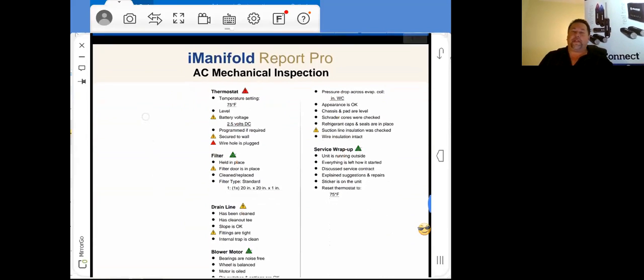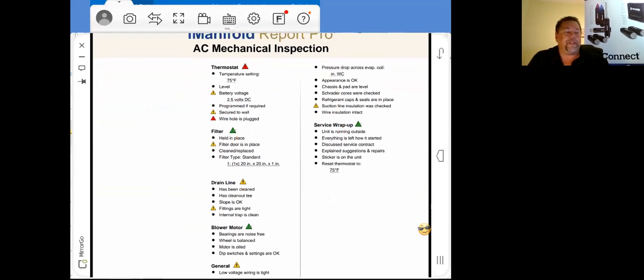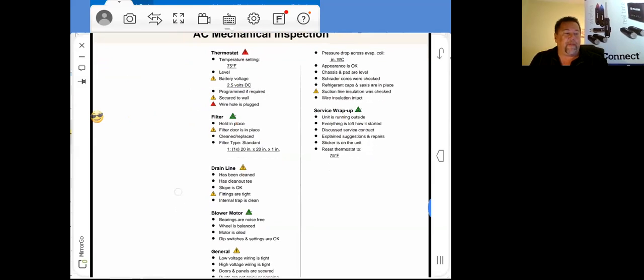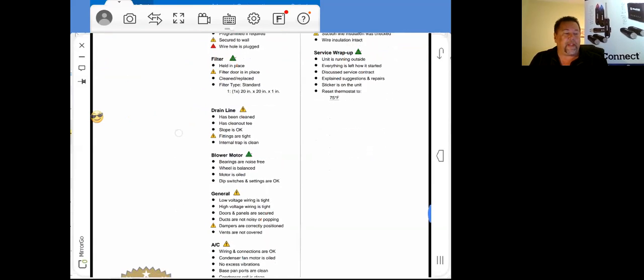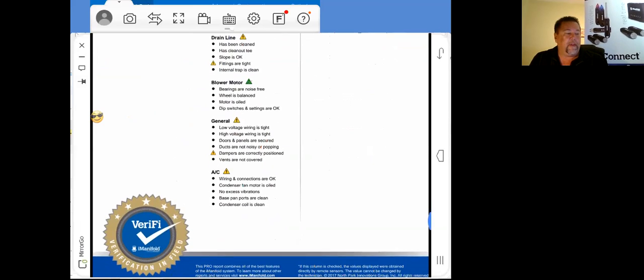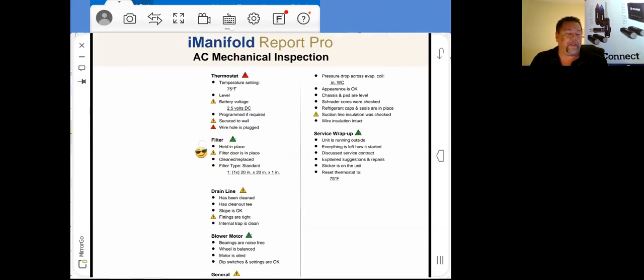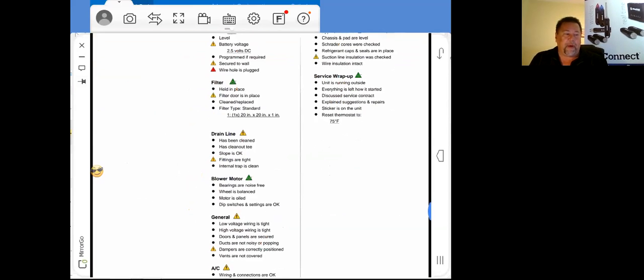Your mechanical checklist - once that checklist is generated, as you can see on the thermostat, we have a red triangle saying it needs attention. We can take a look here - the temperature setting was there, yes it was level, battery voltage was a little low, it was secured to the wall but the wire hole in the back was not plugged. So everything involved with that thermostat, the filter, the drain line - every one of those fields is going to pop up right here, and it's very easy to see what was going on.